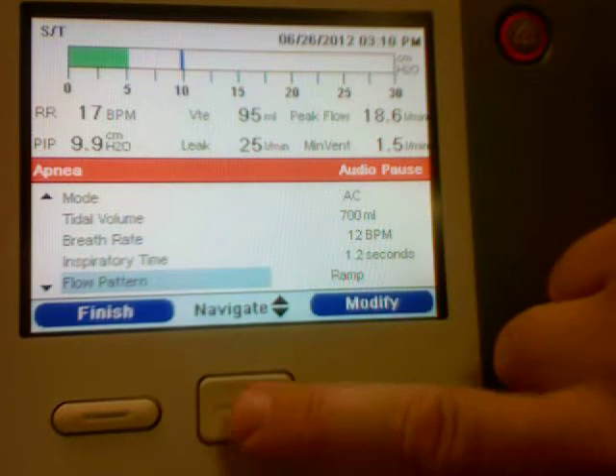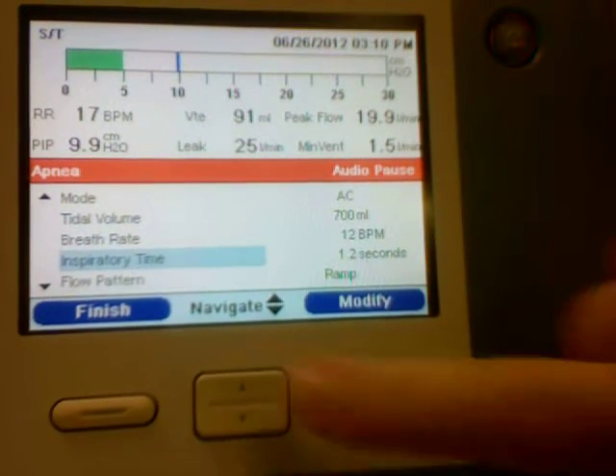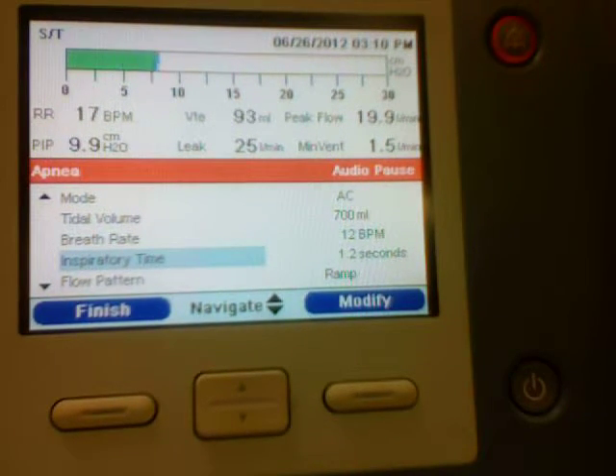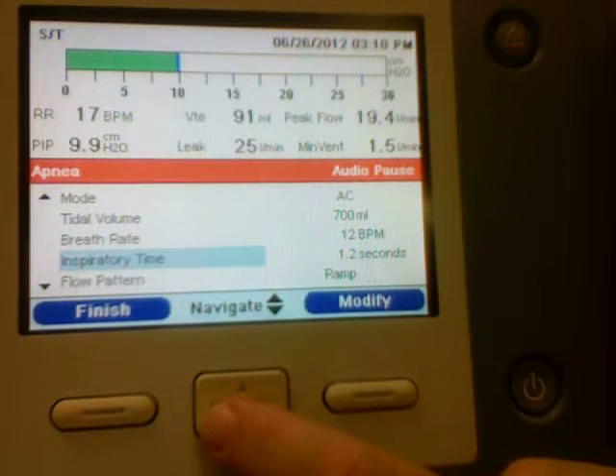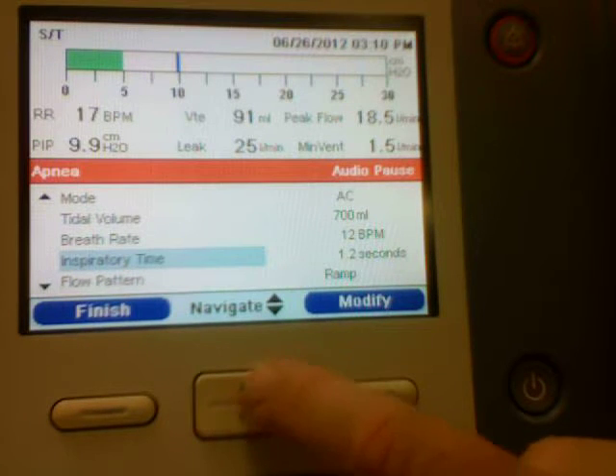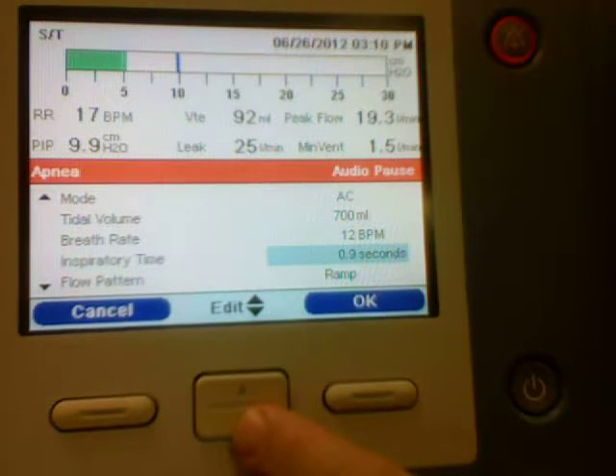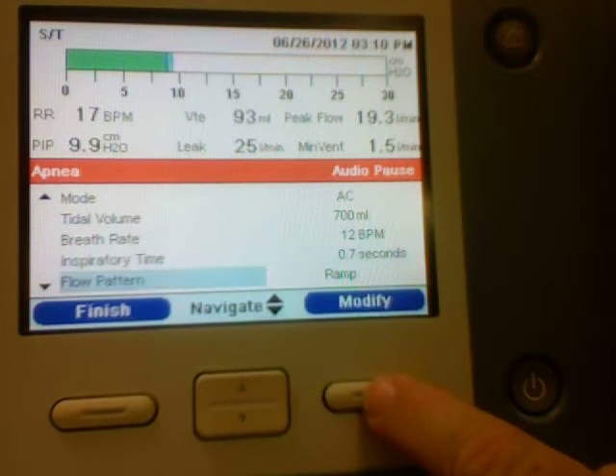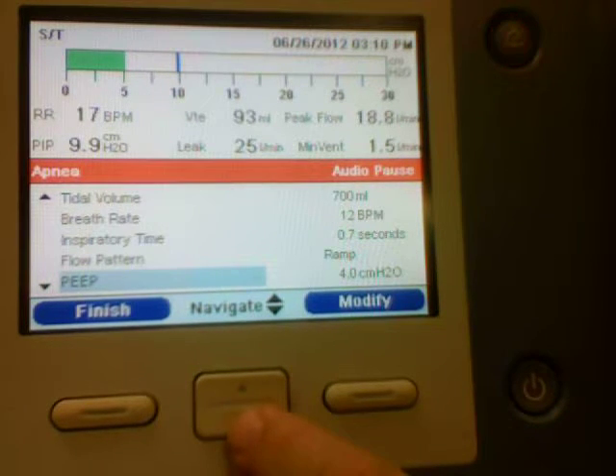Inspiratory time, again, is going to be dictated by how quickly you want to deliver the flow. If I wanted 60 liters a minute, that would be an inspiratory time of, modify, let's go to 0.7. Okay. A little flow rate chart, we can put that on the RT connection so that you'll have a reference point for things like this.